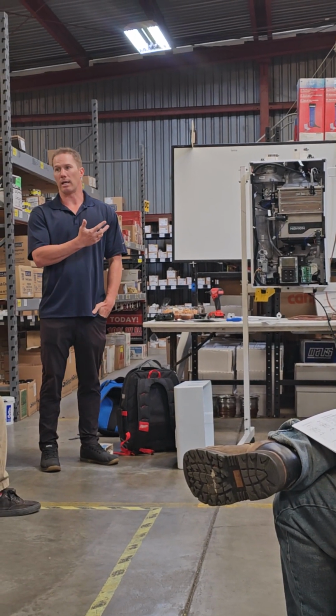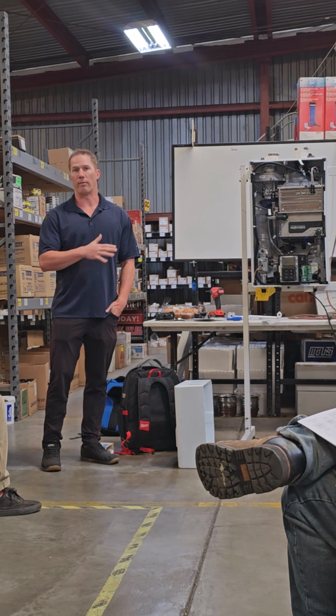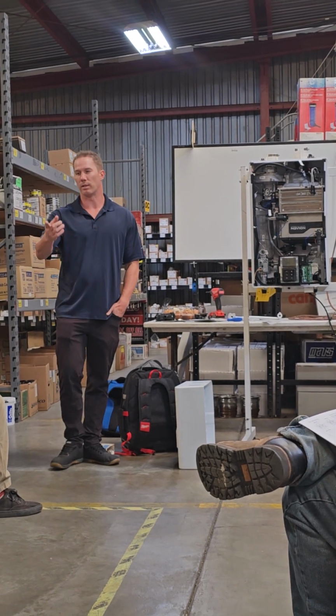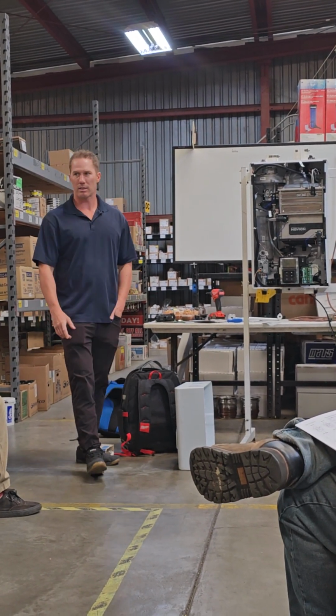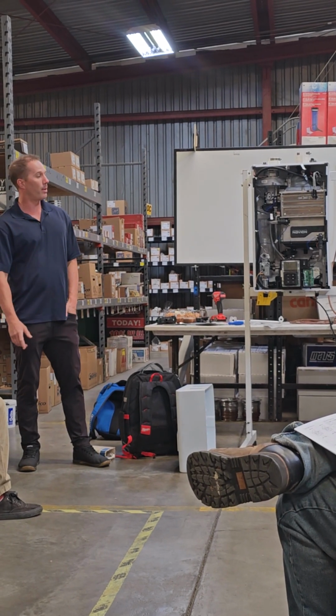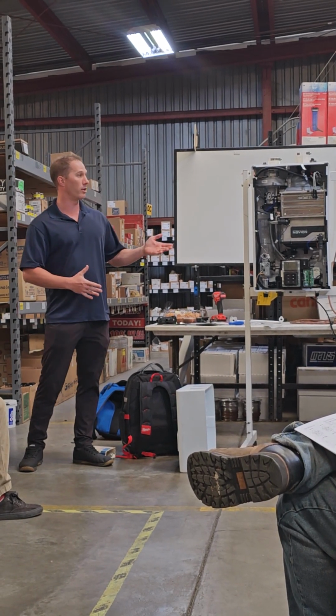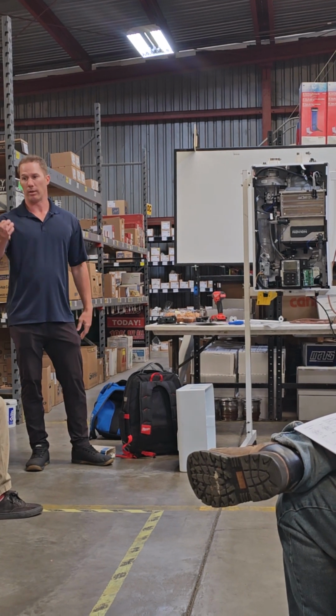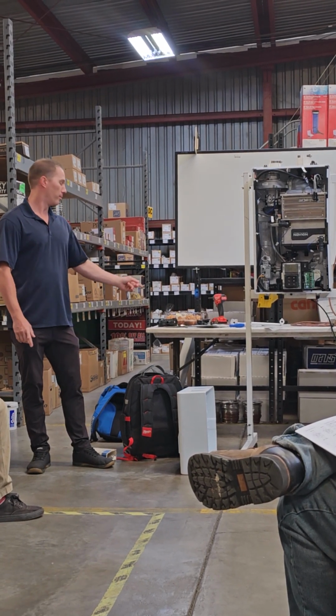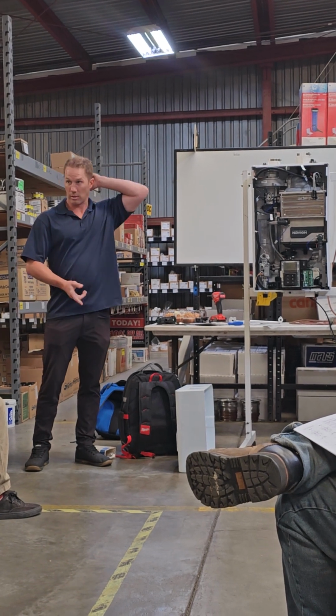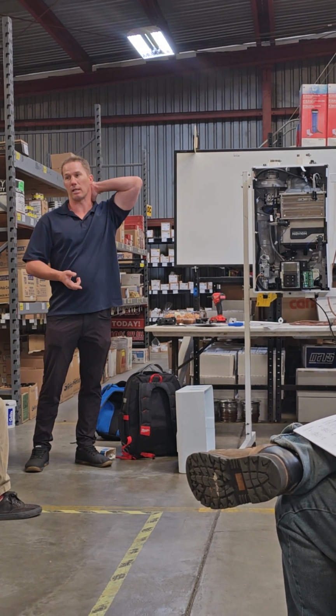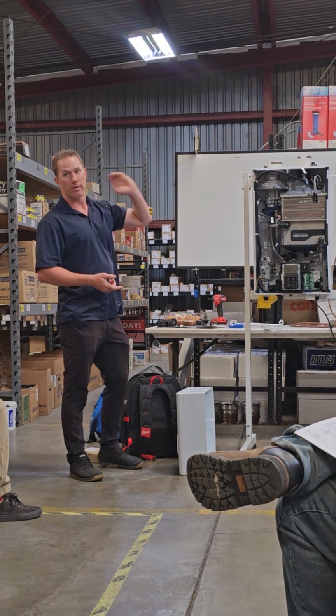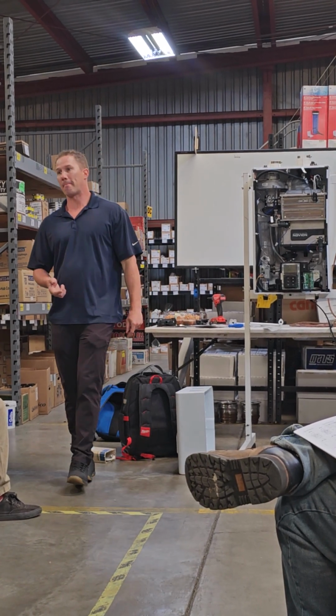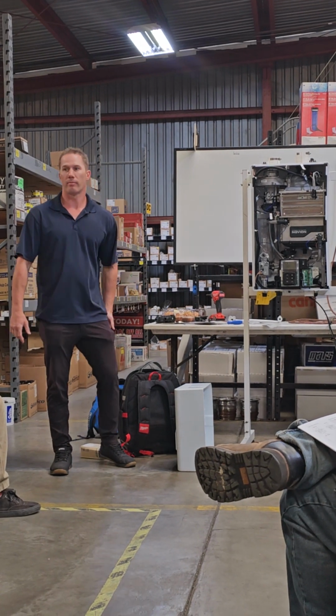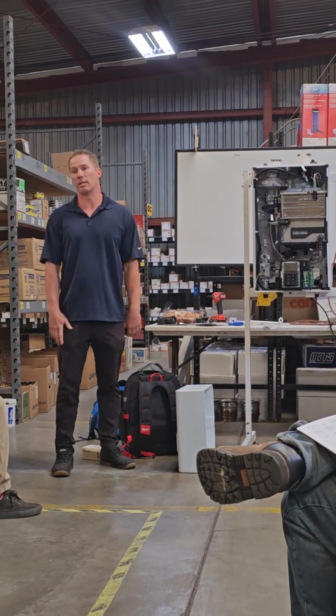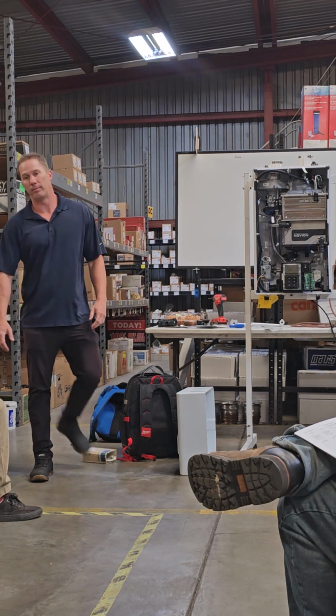The thing a lot of guys like about those ones is they're maintenance free, you never have to do anything, you just put it in and don't touch it again. These peak flow ones, I think you have to replace the media every 3 years. But with that being on, you don't have to service the unit as much. If you keep up with the media on the peak flow system, you never have to clean out the unit because it's never gonna have anything stuck inside of it. So with peak flow, you go from flushing once a year to just changing the media every 3 years, and you don't flush it at all because no scale's ever gonna build up inside of it.